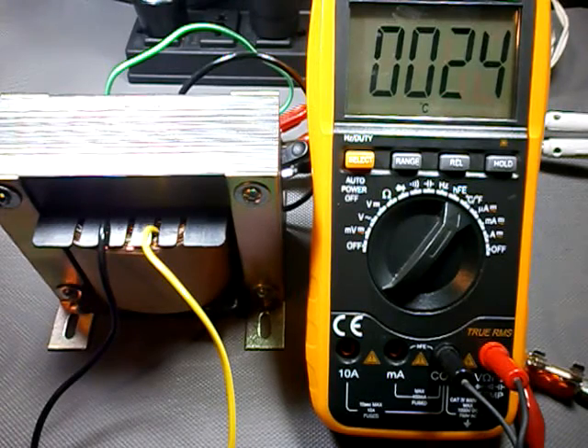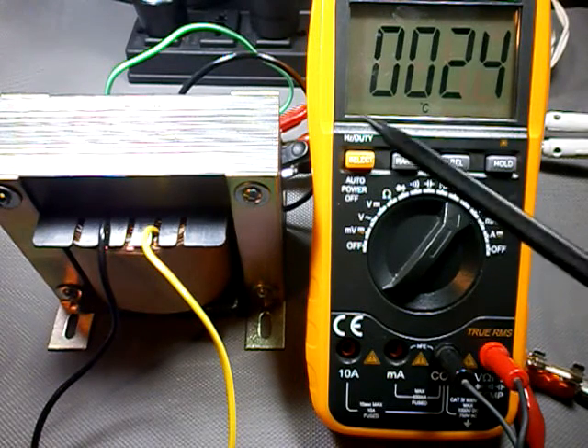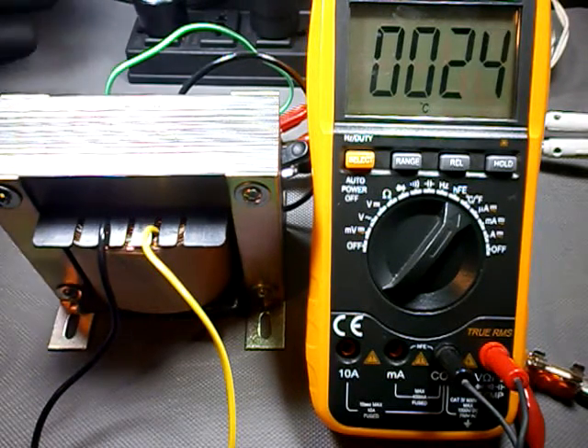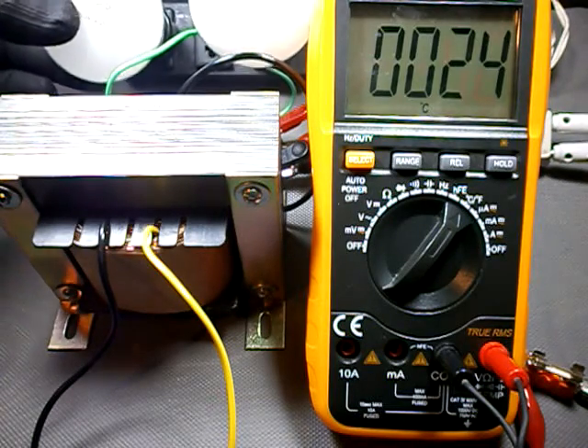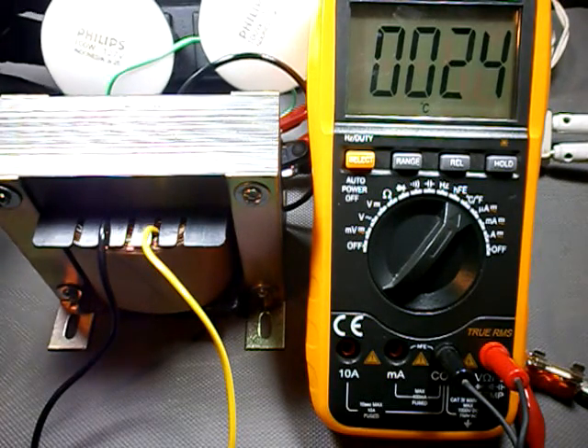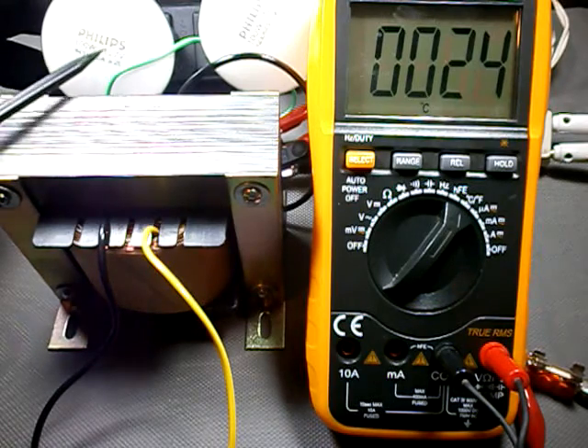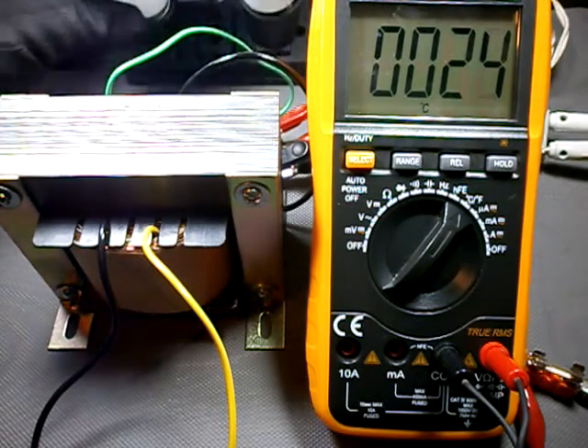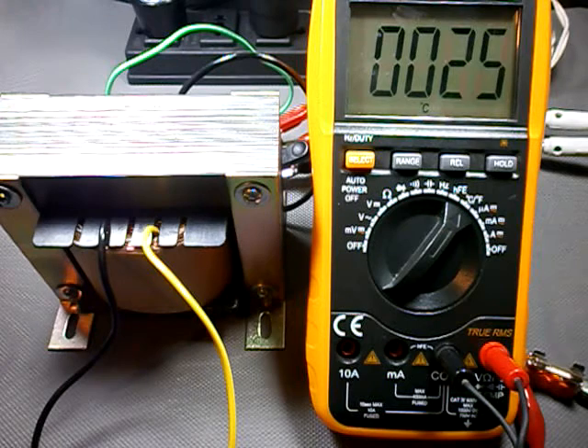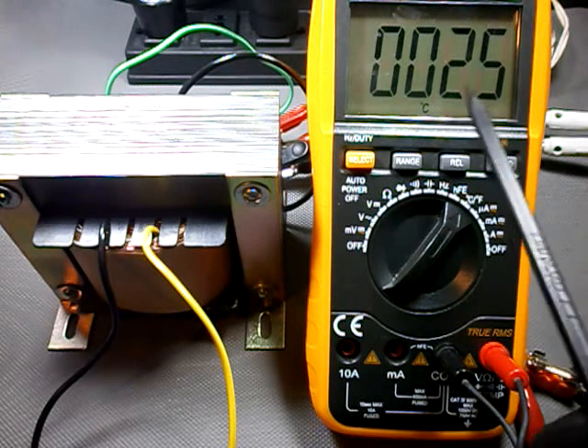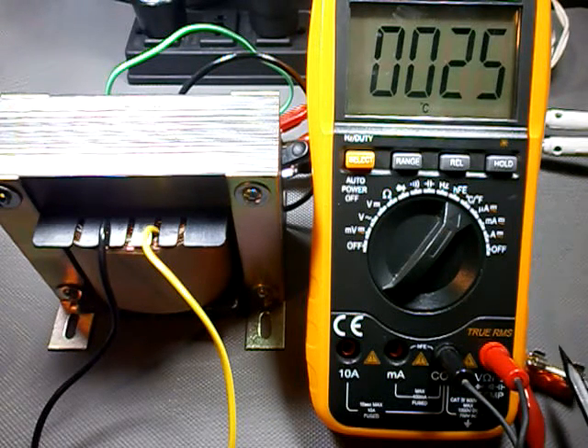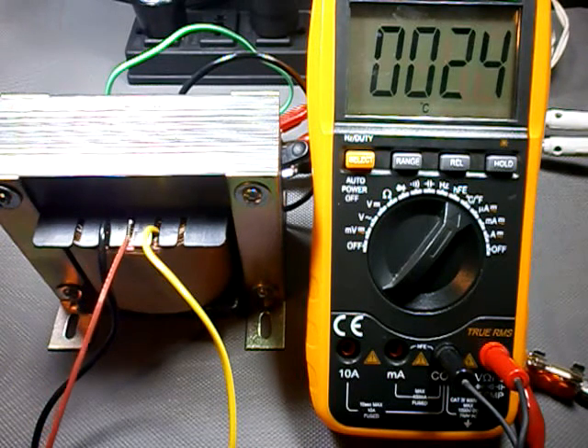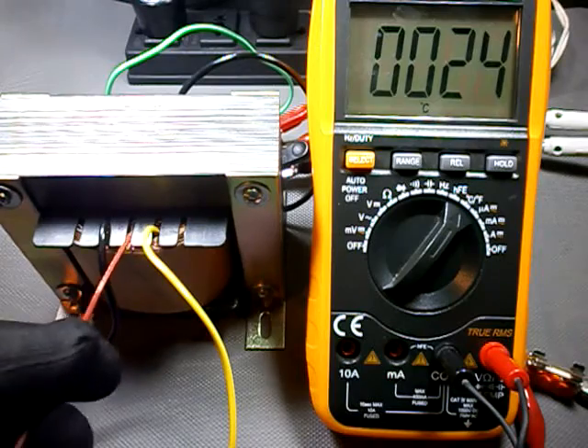The final test is the temperature test. Since we chose paper as the insulating material for the various layers of wire, the temperature inside the transformer cannot go higher than 100 degrees Celsius. Here we have two 100-watt light bulbs that we are going to use as a dummy load. We have an agreeable 24 to 25 degrees Celsius in our workshop. We have a 2-amp fuse in series with the primary in case anything goes wrong, and we have this temperature probe here next to the inner layers.